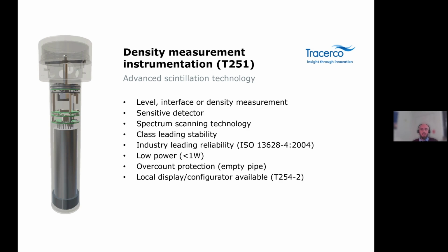This allows the density gauge to operate over a wider temperature range from minus 55 degrees Celsius to plus 60, and this gives an output stability of less than 30 parts per million per degree Celsius. In addition, this method also corrects for any aging in the crystal that might occur over longer periods, and that reduces the frequency of the recalibrations.